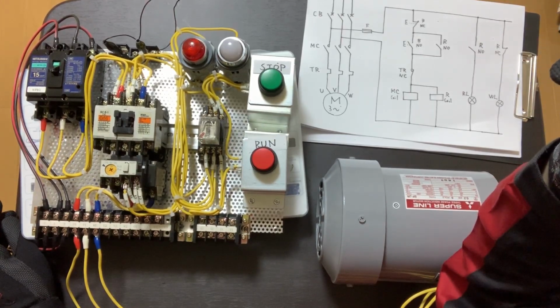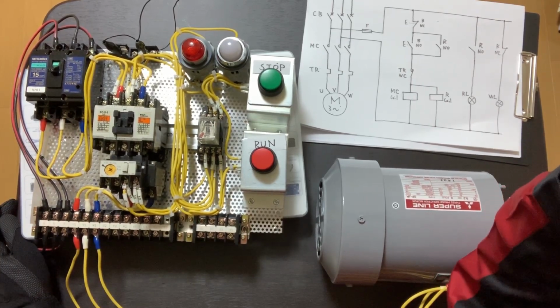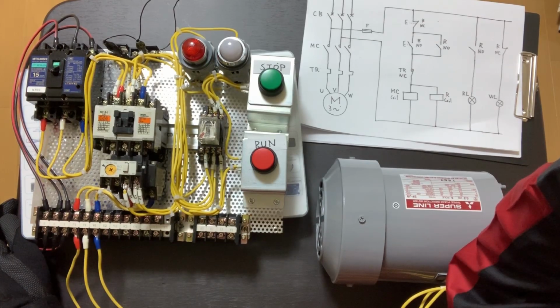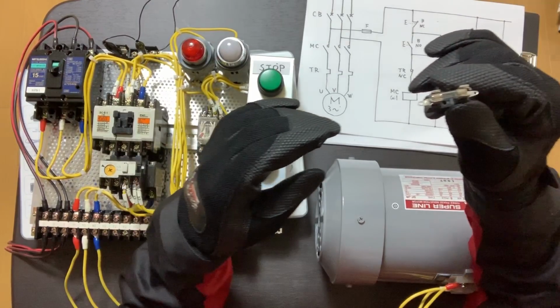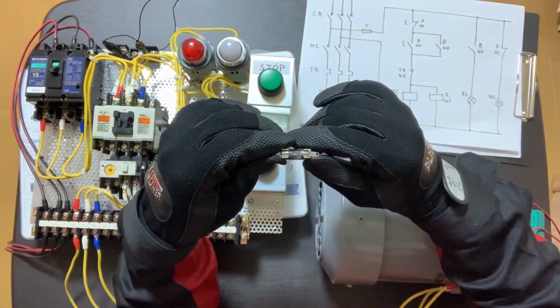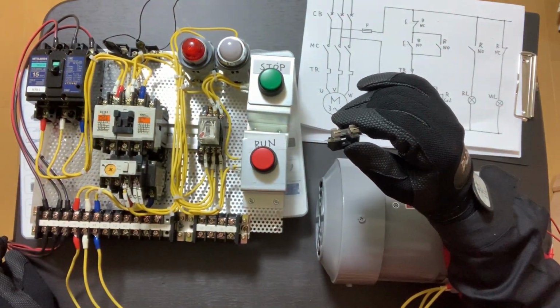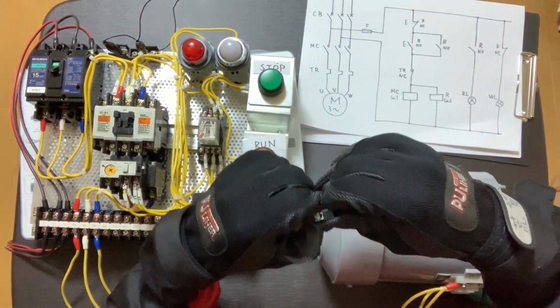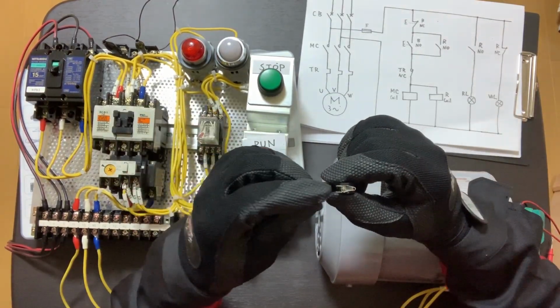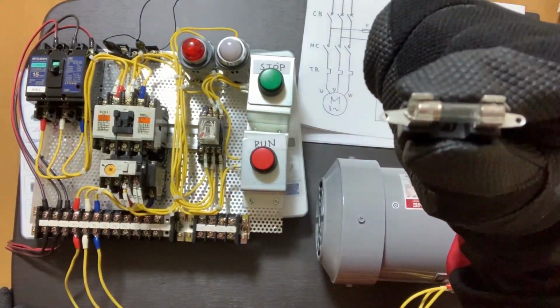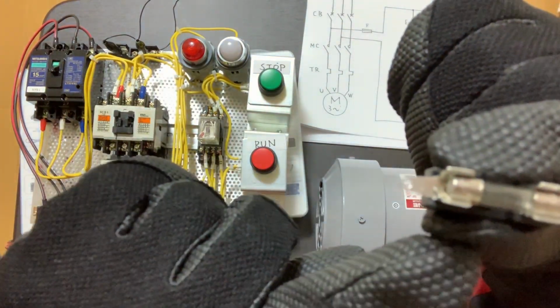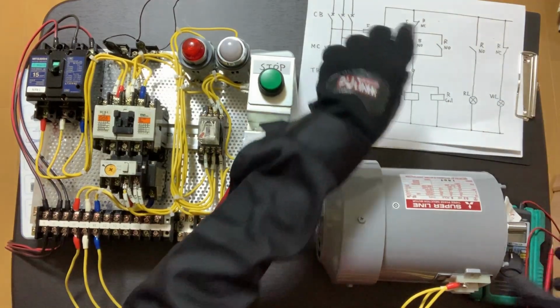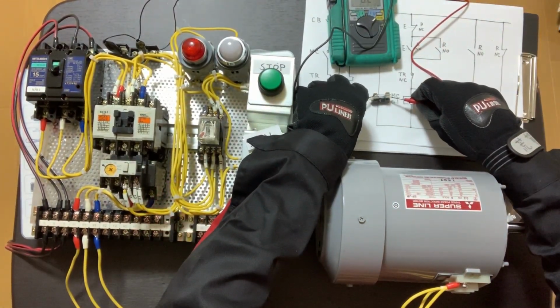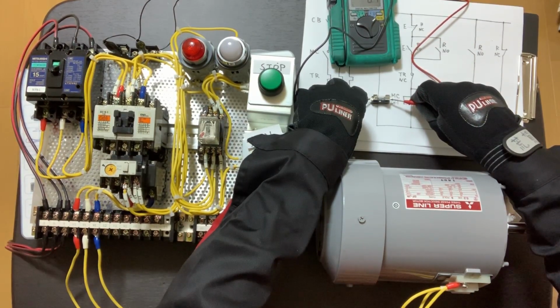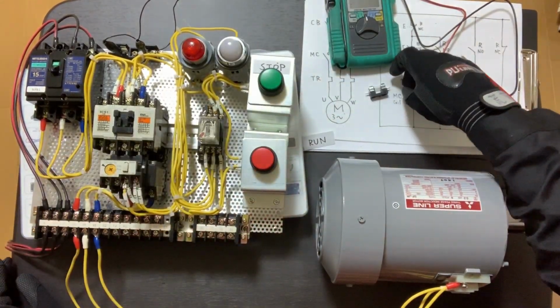Fuse is also one of the most commonly used elements of our protection system, especially for control circuits. They disconnect the faulty circuit if the current reaches a predefined value. And speed and cost are the main merits of fuse. On the other hand, their drawback is that they cannot be reset, so they need to be replaced totally after each operation. It's a little bit too hard to see, but a very slight wire is inside. So it's in a conducting state. Let me check the resistance range. Yeah, it's short. But if some failure happens, it interrupts. Alright.